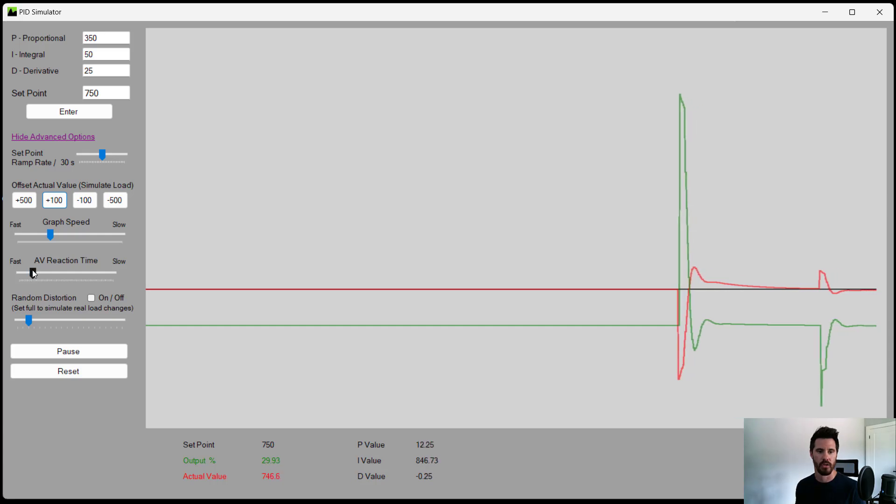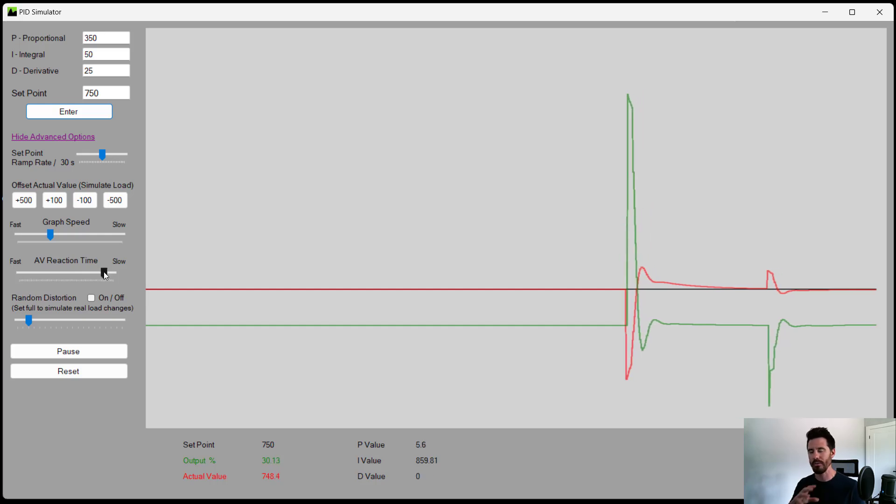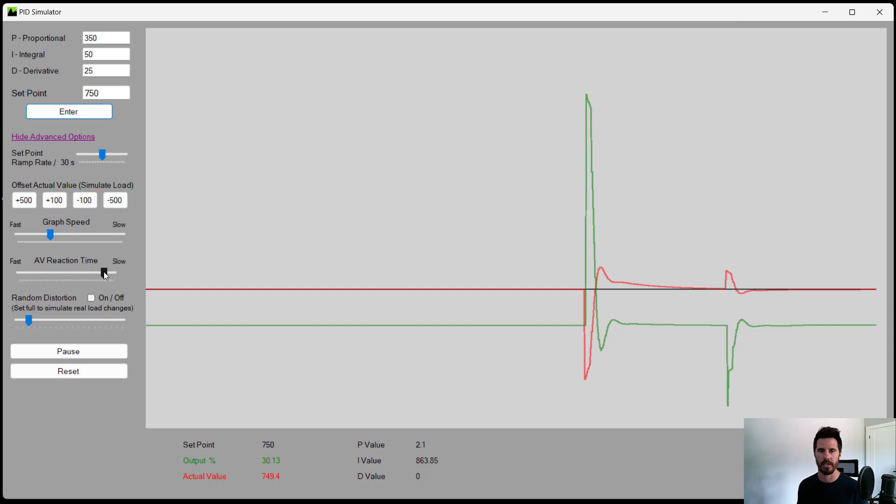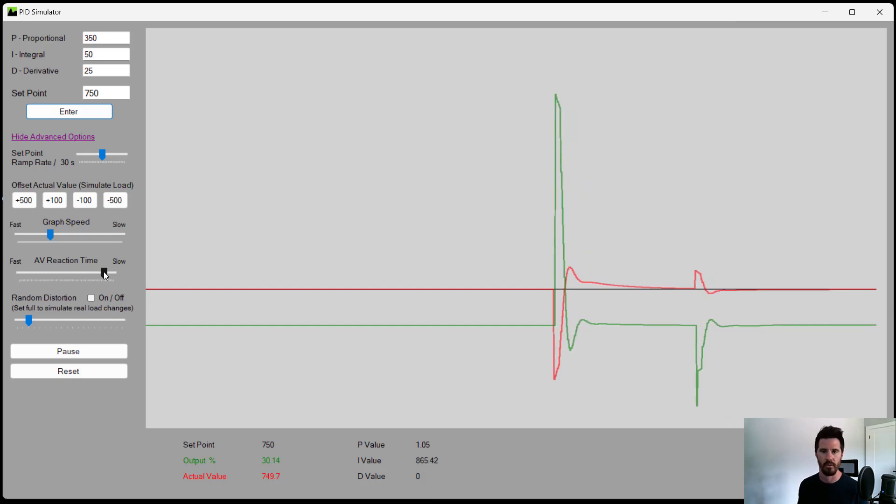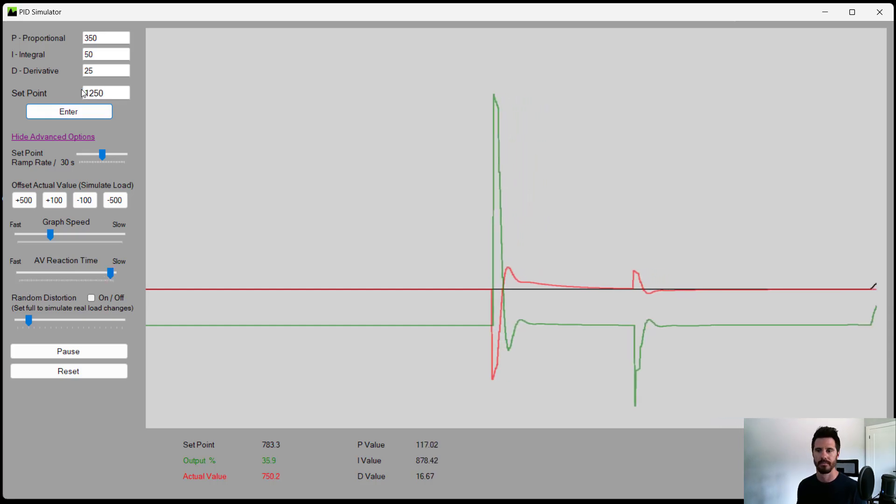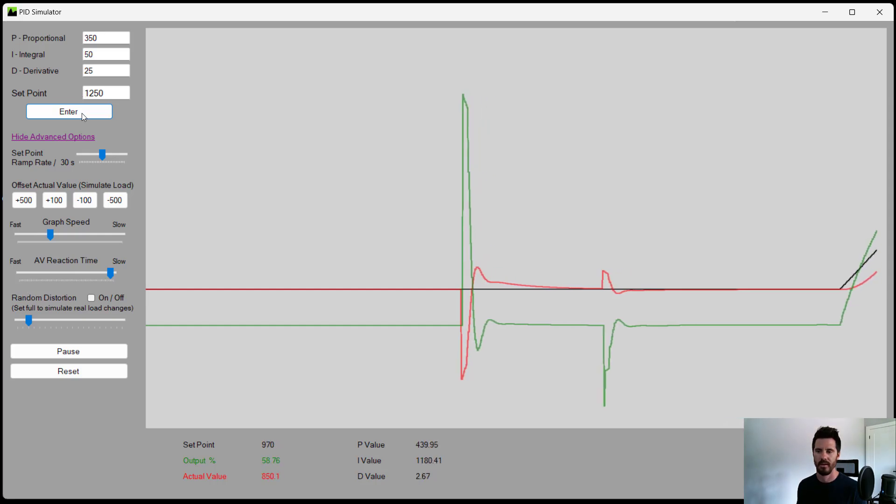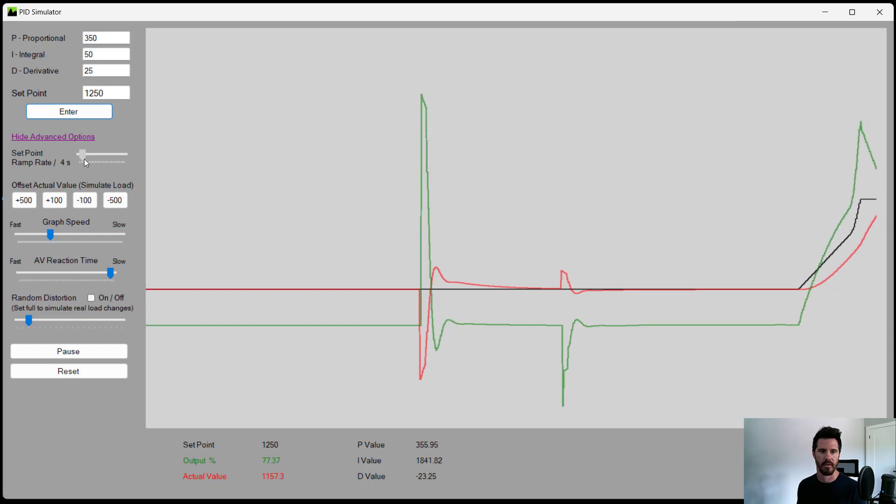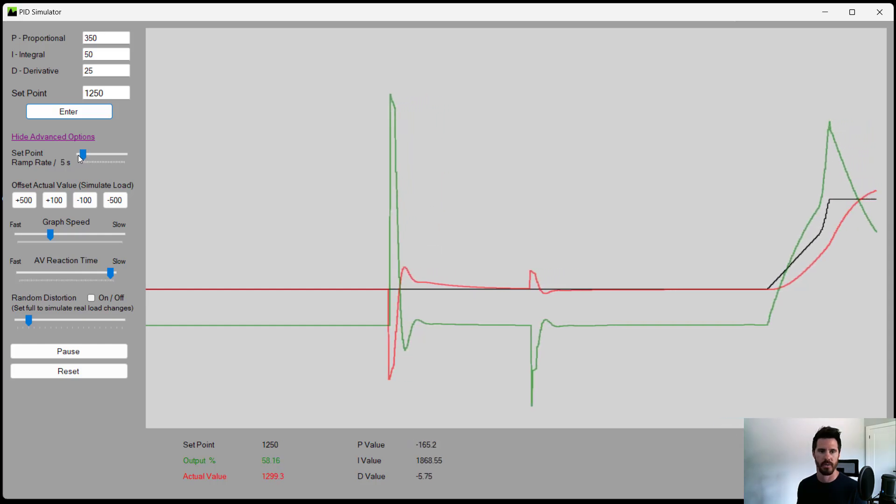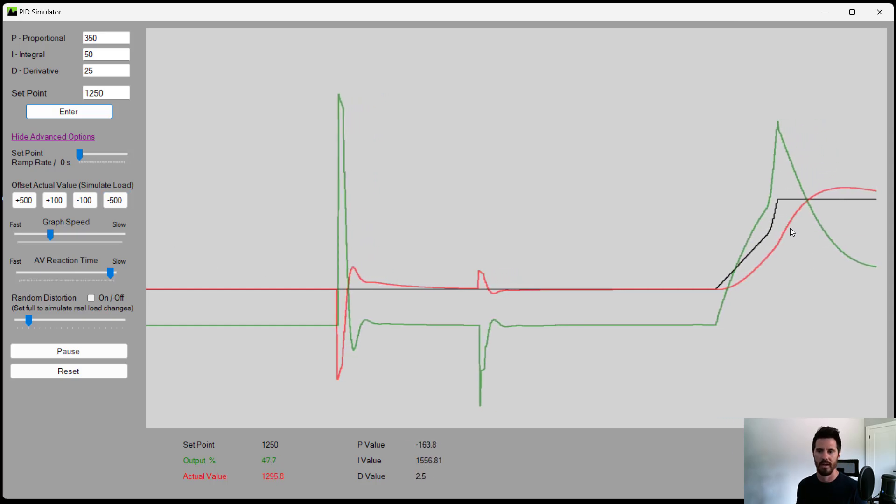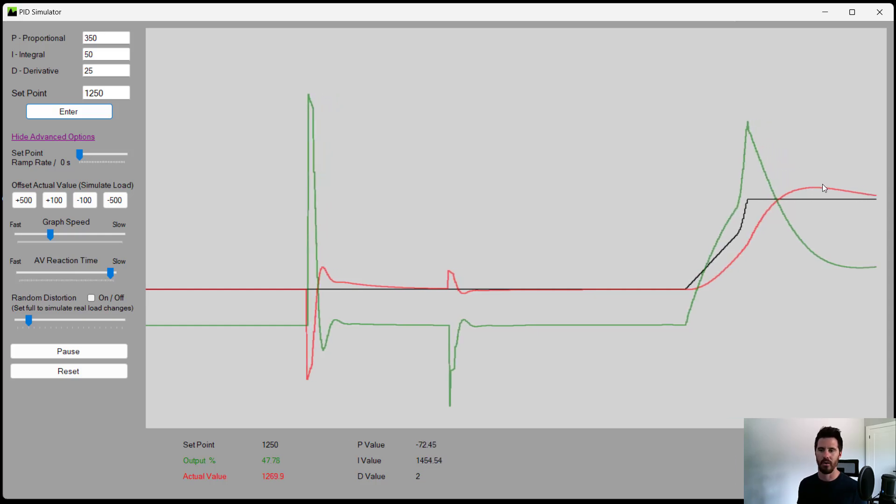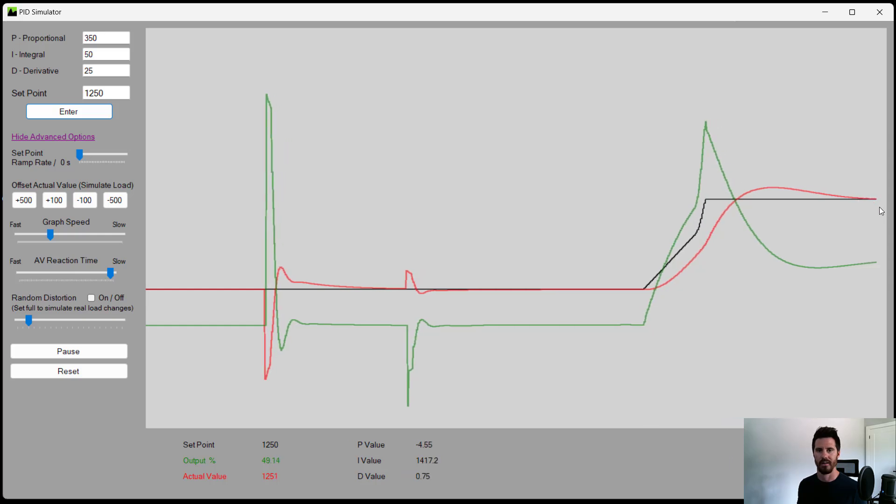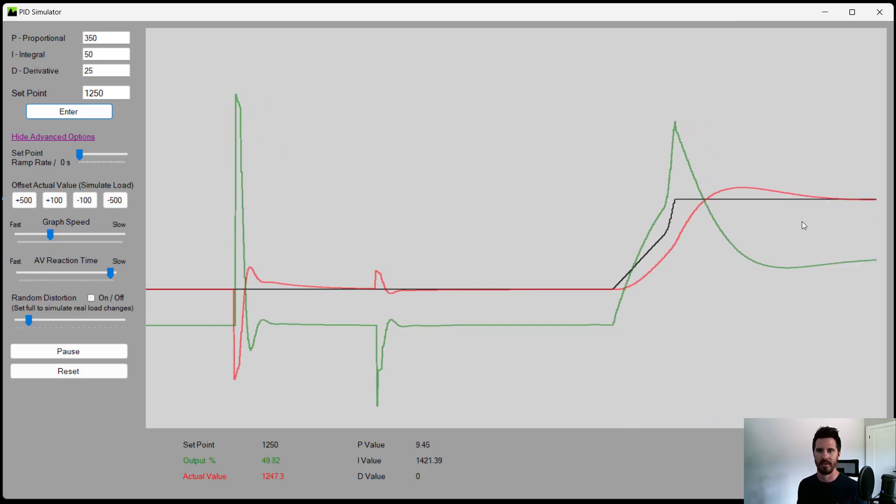We can also slow down the reaction time because if I'm talking about a temperature controller, they're generally really slow acting because it takes a while, whether it's through the boiler or through a heat exchanger, to heat up those hydronic loops or the air in the room. So we'd move this to a slow reacting controller and now change our set point. And I'm going to bring this a little bit faster just so the set point changes as soon as we hit the set point change button.